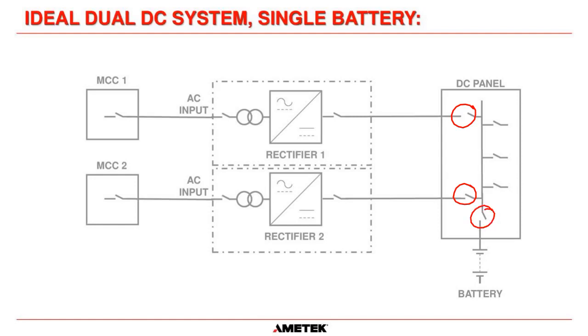So in this circumstance, let's say that rectifier number 1 or charger number 1 fails. What we can do is we can open this disconnect here, we can open the MCC disconnect, and therefore we know we are safe to work on rectifier 1 and do maintenance or even replace it if we absolutely have to. So it gives us lots of flexibility. And while we're working on rectifier 1, we know we have rectifier 2 here working absolutely fine, charging the batteries and keeping the load circuits powered. So this is a very, very good design.